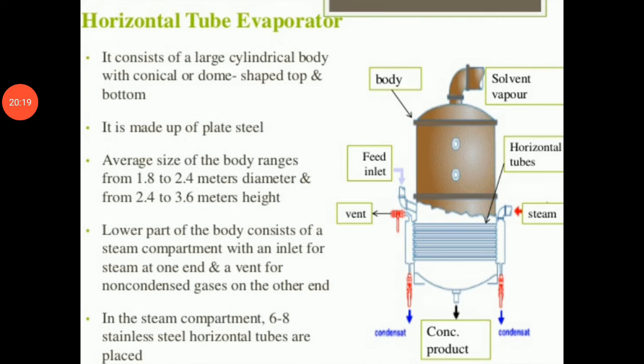Any room where evaporation is carried out by this apparatus must have good ventilation to remove the vapor. Otherwise, the room is quickly filled with a dense fog of condensed vapor, and water falls from the roof and runs down the wall. Fans fitted over the pan not only remove the vapor and prevent condensation in the room, but also accelerate the rate of evaporation by quickly removing saturated air from the surface of the liquid.